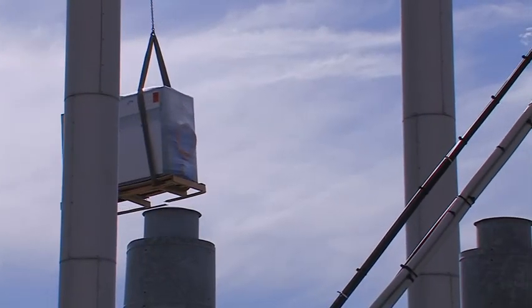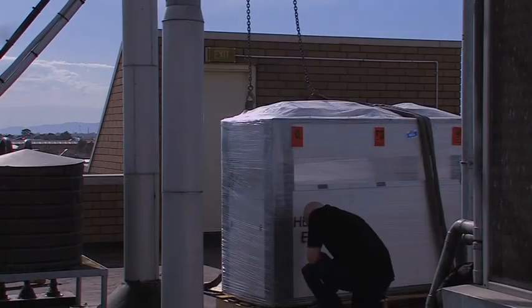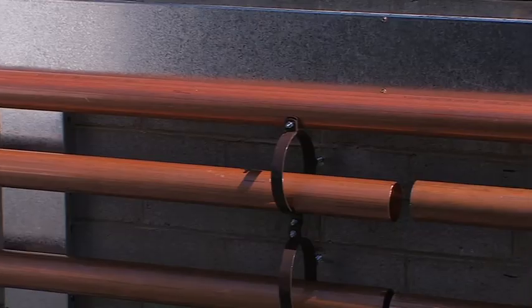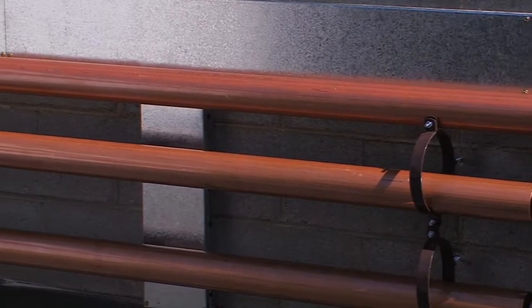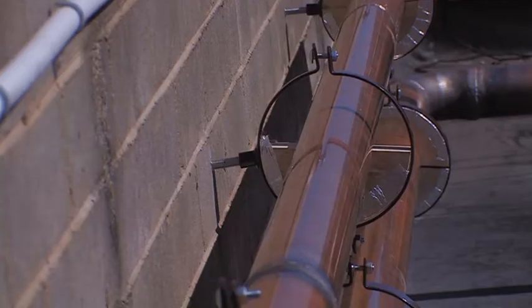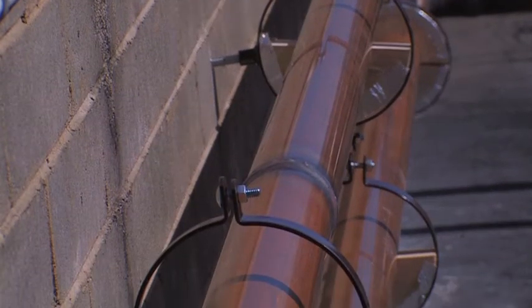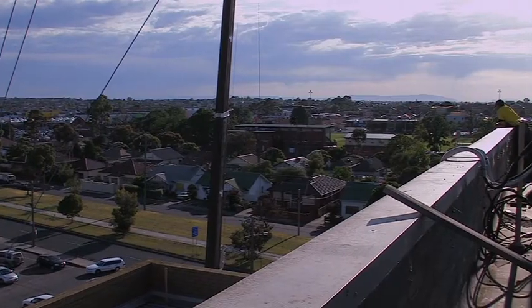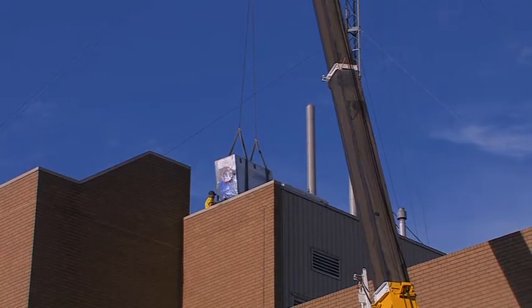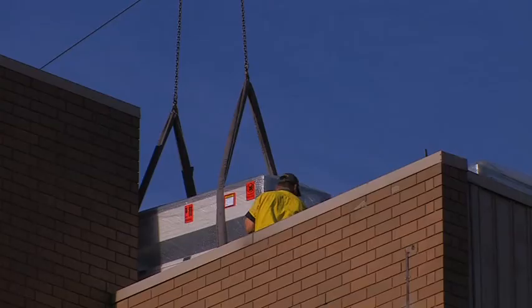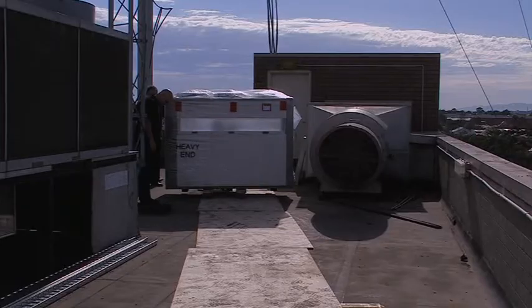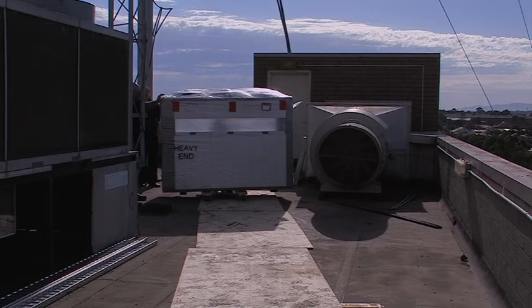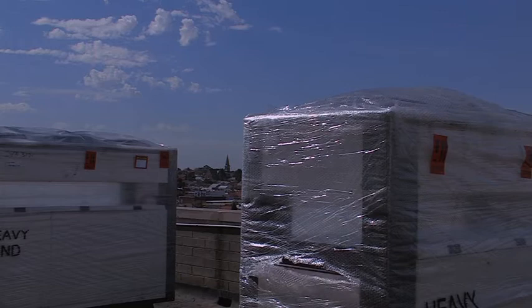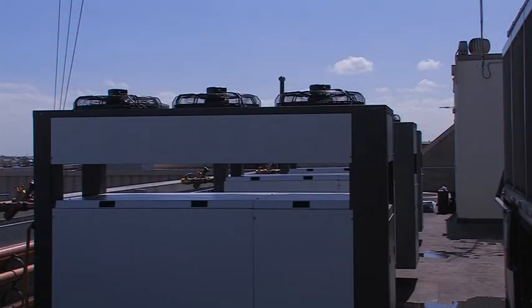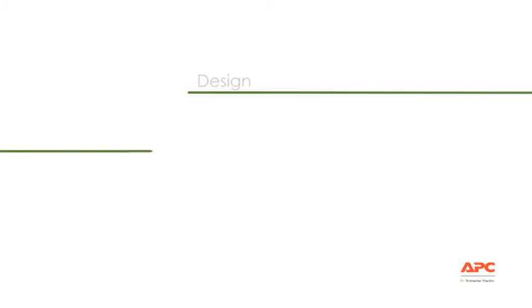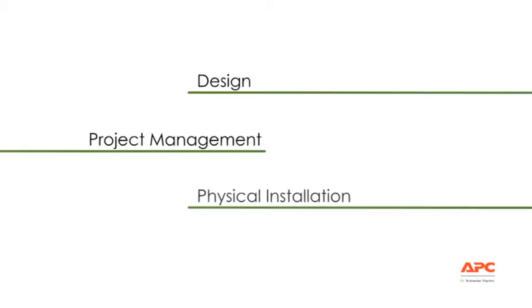During Phase 1, the chillers were delivered and installed by APC on the roof of the building. Mechanical piping was also installed through the risers of the building to the main chilled water distribution unit located in the data centre. The positioning of the chillers had to be completed in less than an hour because of the location of the crane and obvious traffic concerns. The project team of 15 people from APC were involved in the delivery of Phase 1, which included the design, project management and physical installation.